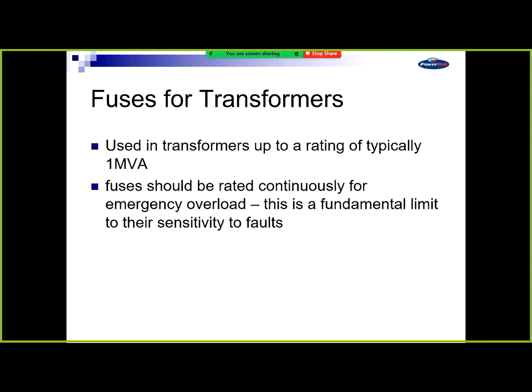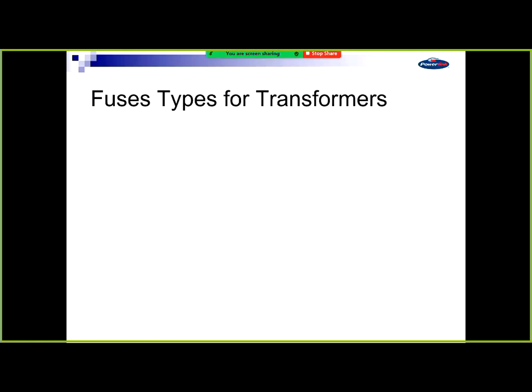For lower voltage distribution, Energex, Ergon, Energy Queensland, they're called now, mining sites, big factories, things like that, where they've got these smaller transformers, fuses would be all that they need. Your fuse needs to be rated over the emergency overload, and that limits their sensitivity. For ours, it's not really a problem. We've got a high fault level, a low rating transformer, so the sensitivity is not an issue to faults.